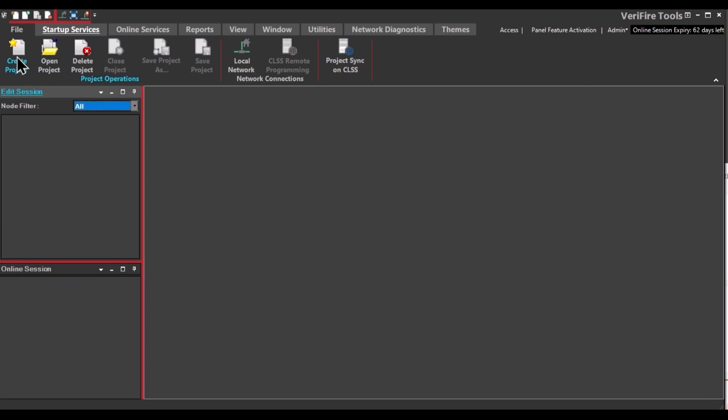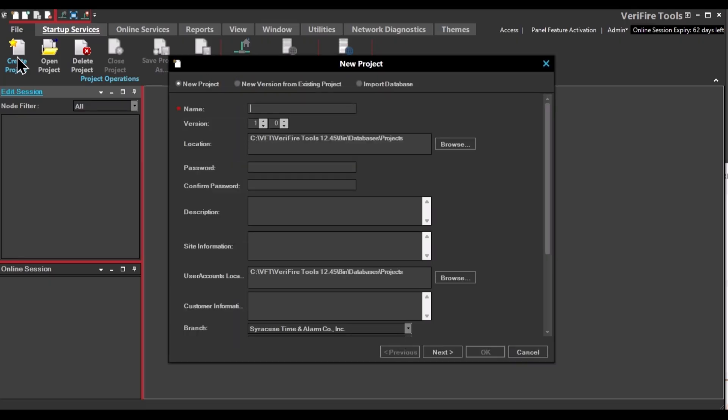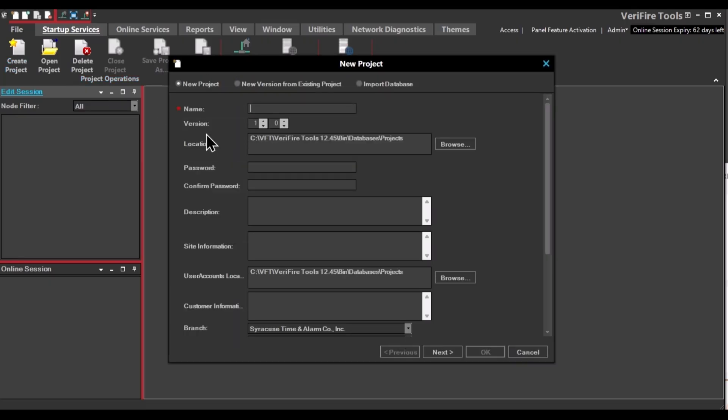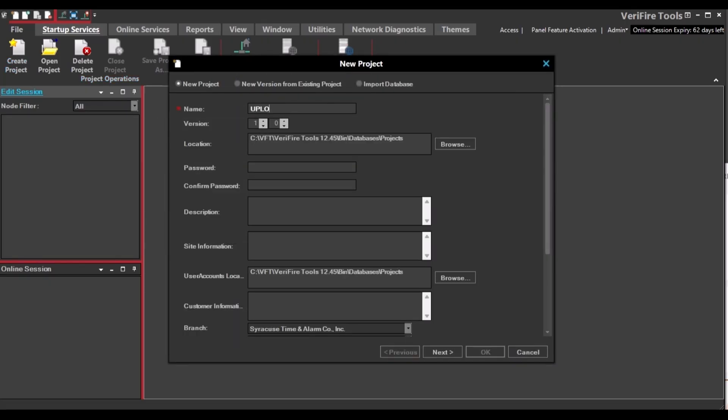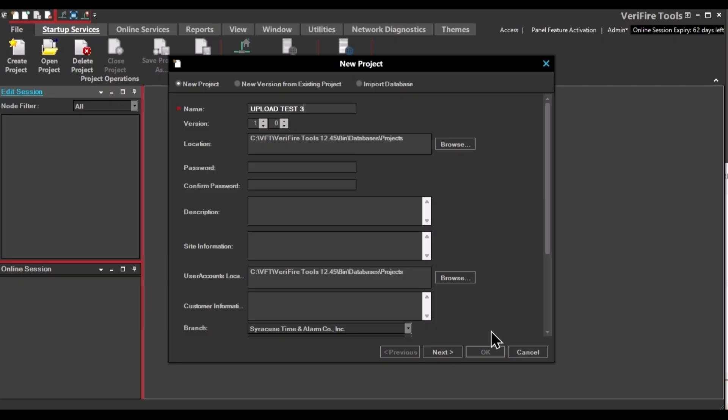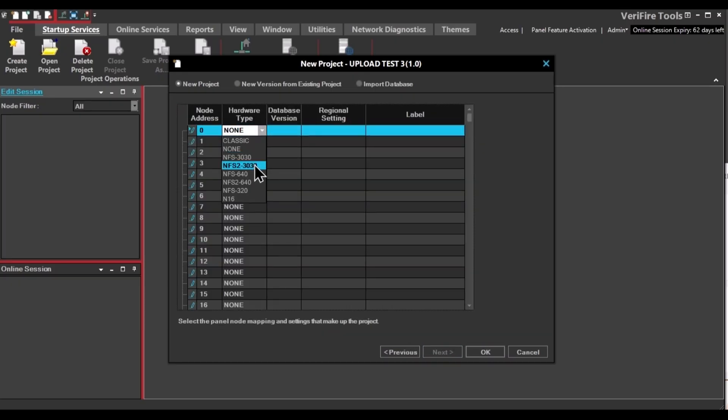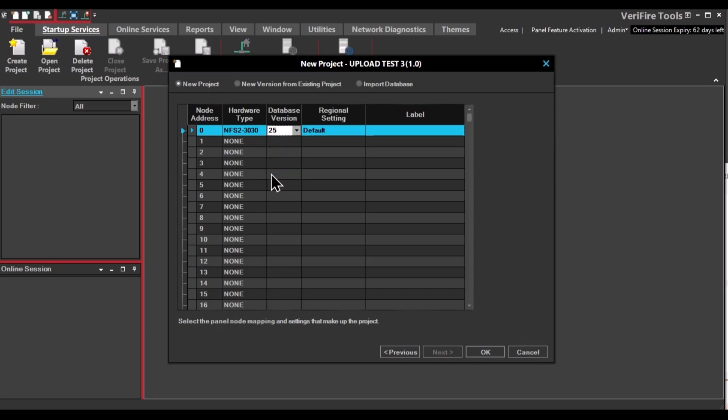You can also create a blank database and upload the panel data into that. Enter your file name and then click Next. You need to select the hardware type that you're going to be uploading. In our case, a 3030. It has a database version of 31, but we'll choose the wrong one on purpose so that you can see that it doesn't matter. It just overwrites it. You can enter a panel label. And when you're done, click OK.